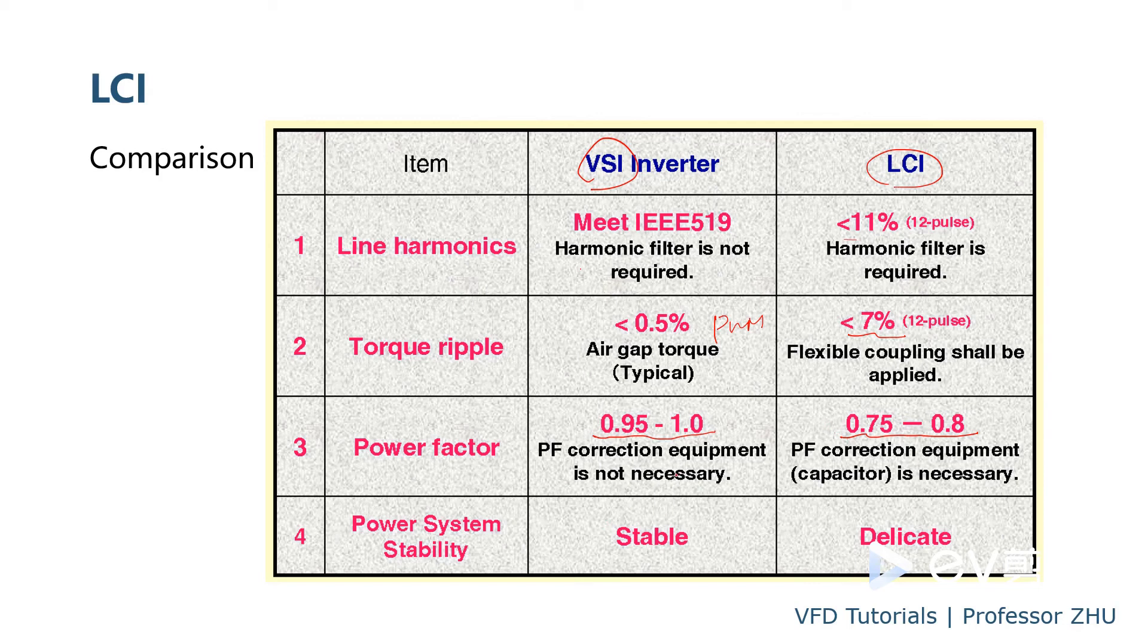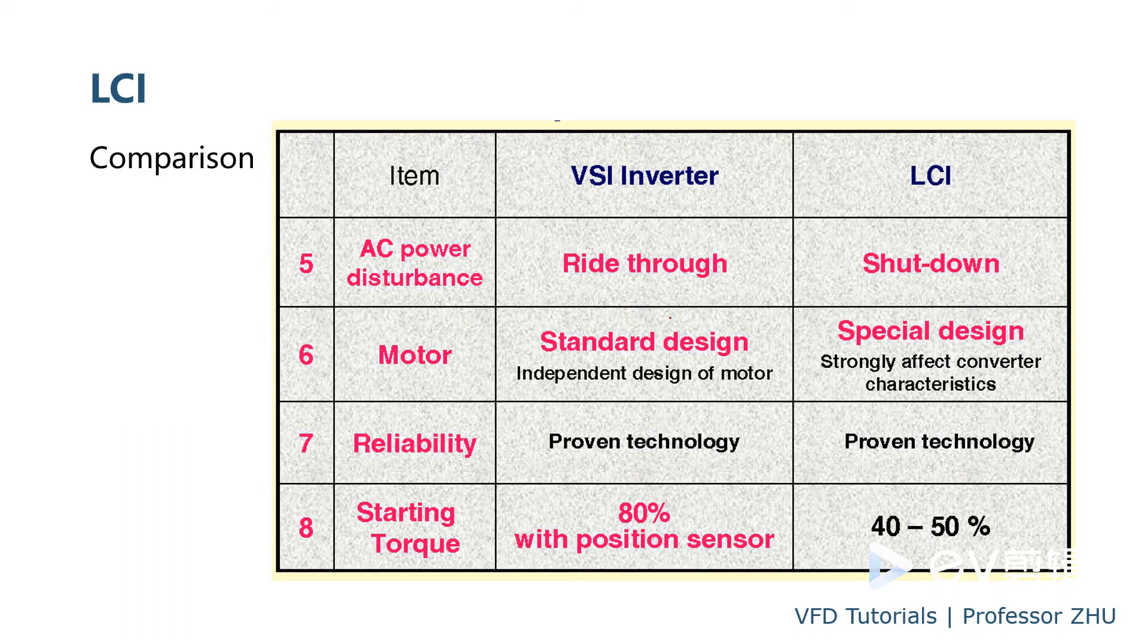And also harmonic is good. Typically VSI will use 24-pulse or 36 or even higher rectifier numbers. But LCI typically is 12-pulse maximum. So still very high harmonic, cannot meet the IEEE standard. So you need a harmonic filter or power factor correction. And torque ripple, VSI uses PWM technology. So output current waveform is very good, very sinusoidal. But this one is a trapezoidal waveform. So the torque ripple is very high. Power factor, as we said, because of the diode rectifier. And this one, SCR rectifier, because of the lagging of the current on the input side. So power factor is also low.